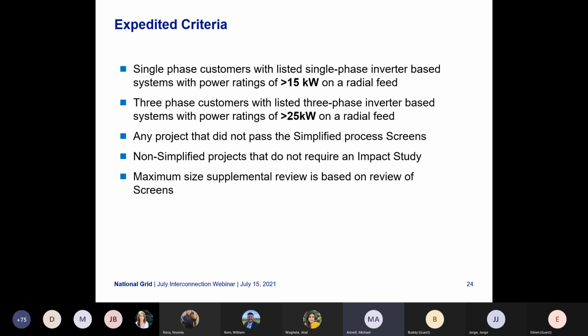Any project that did not pass the simplified process screens, typically many residential projects that have an overloaded transformer, would then become an expedited project if there is some construction needed. Also non-simplified projects that do not require an impact study. So if they don't require an impact study but they're not simplified, they will fall into that expedited window. The maximum size of supplemental review is based on the review of these screens. Next slide.